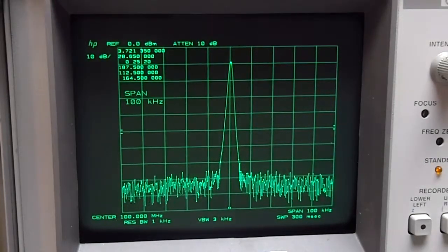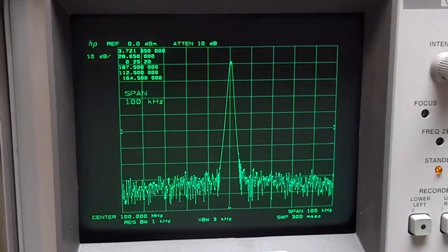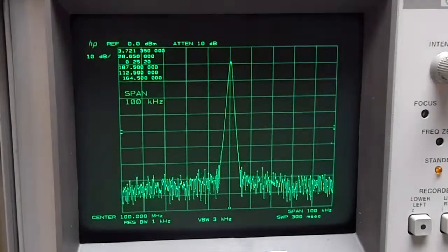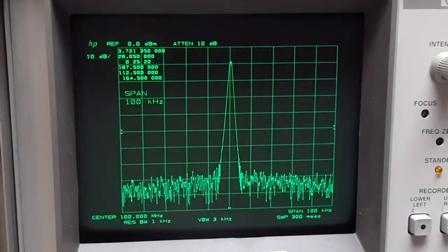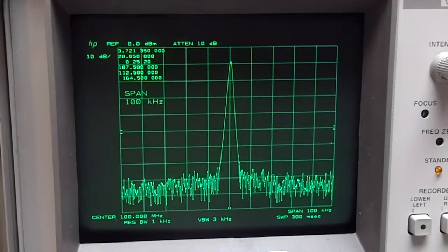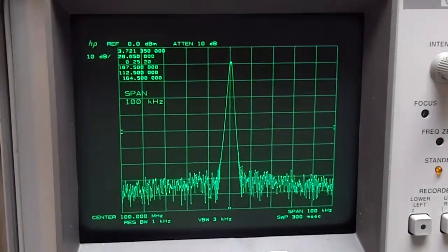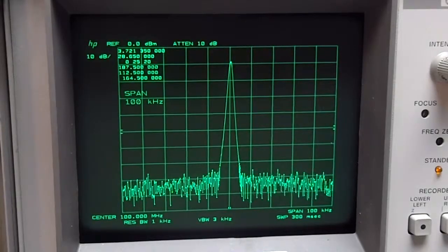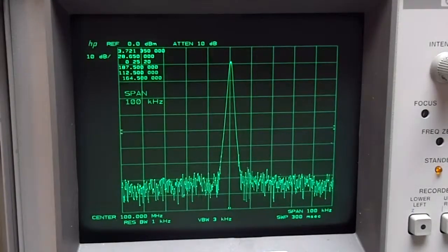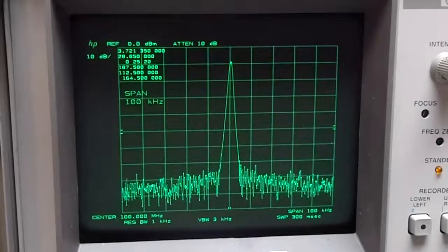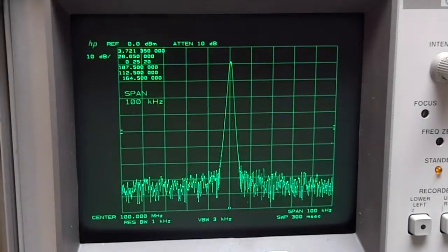And when you use the shift key to remove that, now you can just enter in a center frequency, and voila, the offset's removed, and you're essentially commanding that frequency come out of the YIG if you're in 0 span. Okay?